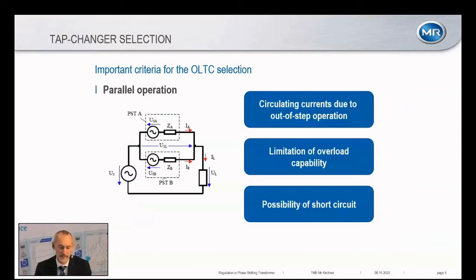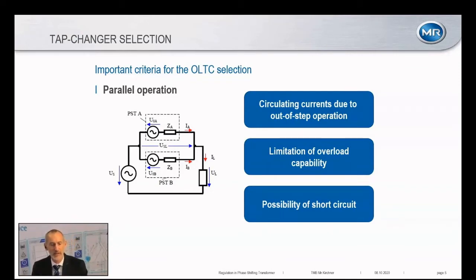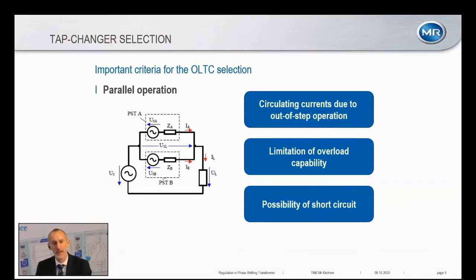It is very important to clarify all these issues up front. Another important consideration is parallel operation: phase shifting transformers are quite often operated in parallel. The OLTC is not always operated synchronously on both units — there will always be a time delay. This creates a circulating current between the phase shifting transformers, which adds to the load current. While this may not be a major thermal issue for short periods, the on-load tap changer must be able to handle this circulating current.